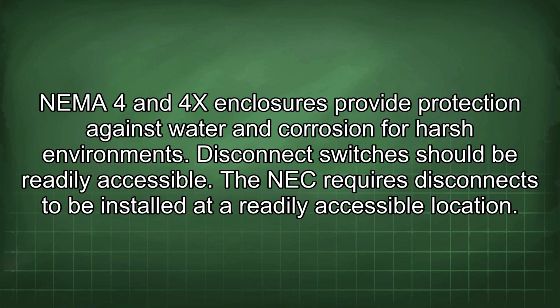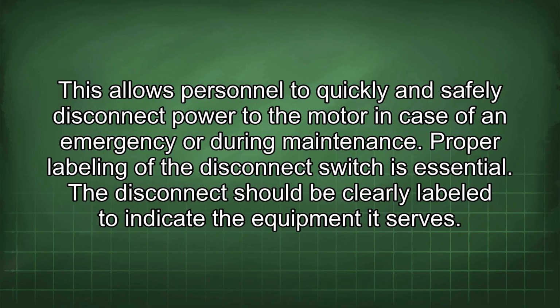Disconnect switches should be readily accessible. The NEC requires disconnects to be installed at a readily accessible location. This allows personnel to quickly and safely disconnect power to the motor in case of an emergency or during maintenance.